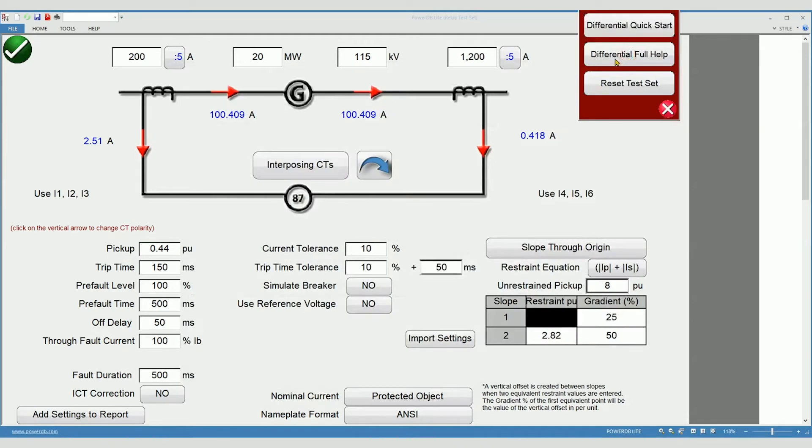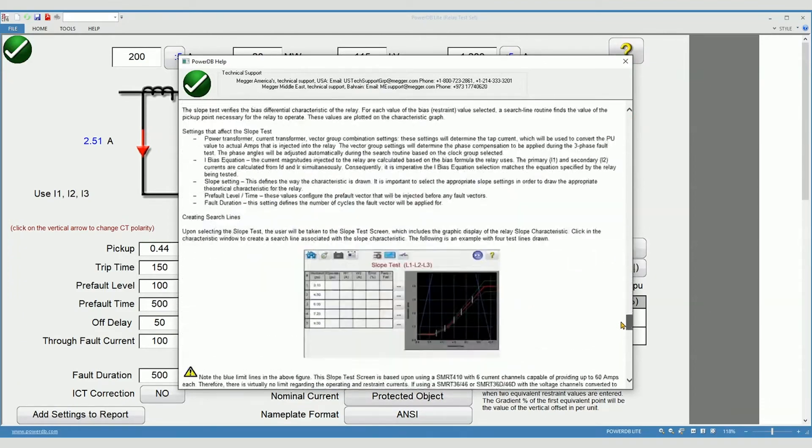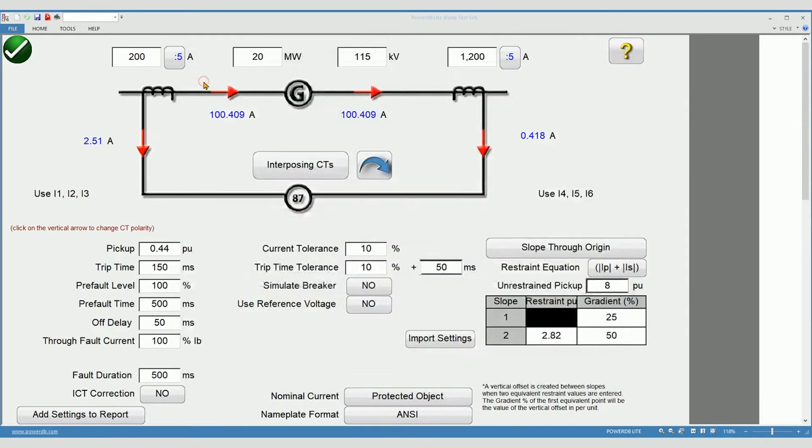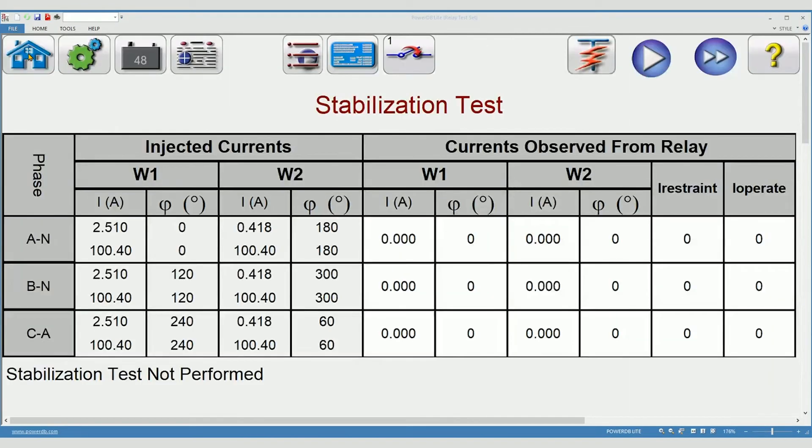The differential full help includes the quick start and near the bottom, it includes step-by-step how to test differential relays. Notice the location of the generator, CTs, and relay. Now I will move to the motor differential test screen.